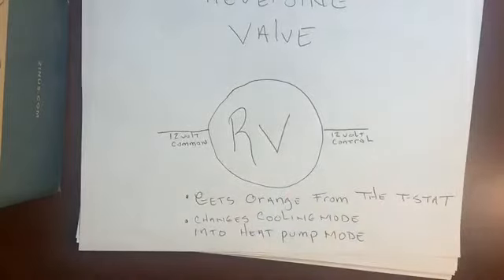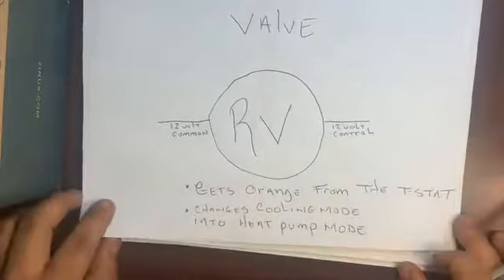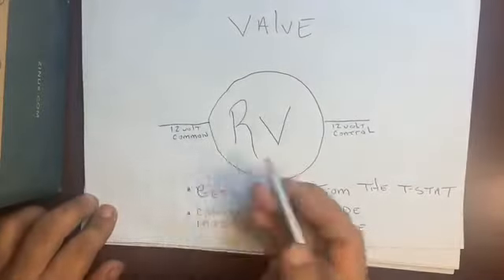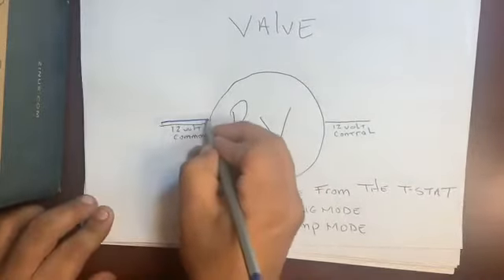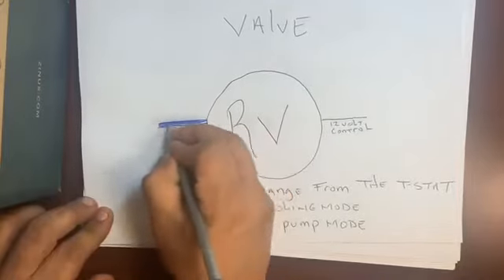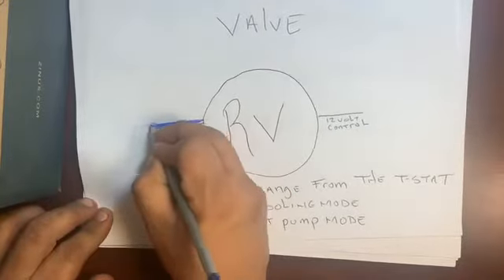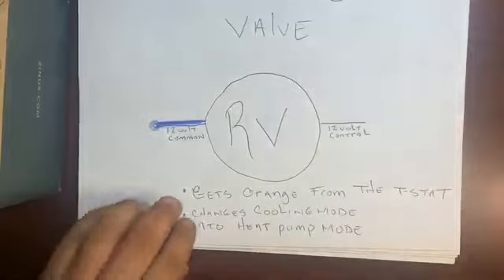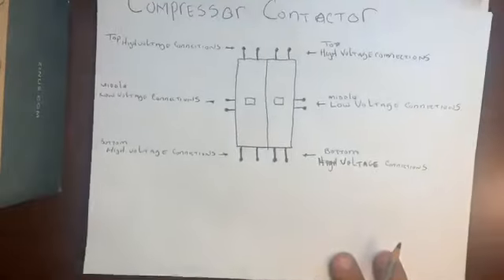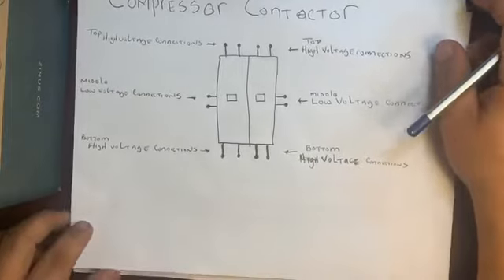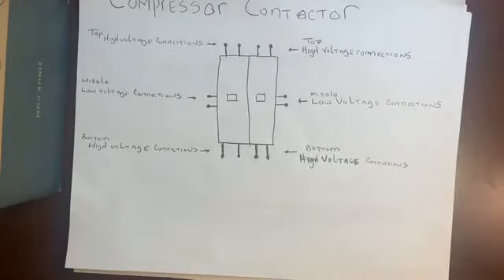And again, a relay is a relay is a relay. Every relay has a low voltage control. So we're gonna find the common. We're gonna make that blue. Blue all day. Just blue because common gets its blue. We're gonna go past the reversing valve. Compressor contactor. This is the other relay that's outside in the condensing unit. Looks a little complicated, it's not.